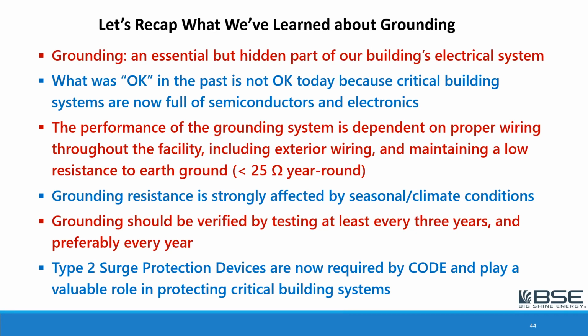So as you saw from the AEMC data, grounding resistance is strongly affected by seasonal and climate conditions. And so what should we do? We should check our grounding at least every 3 years, and preferably every year. If you've never done it, and we find a surprising number of facilities have never done it, it should be done. And then also, we really strongly recommend Type 2 surge protection devices.